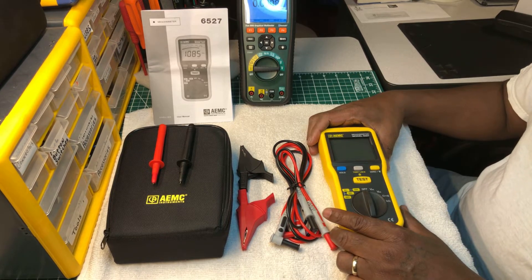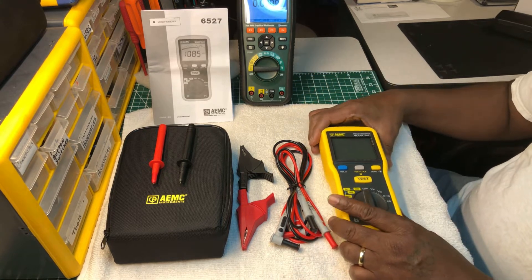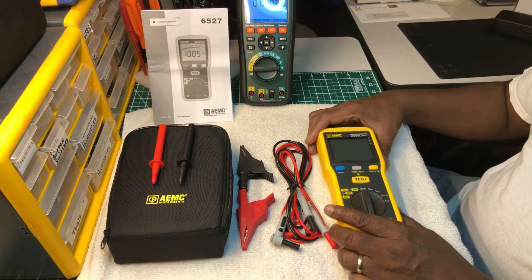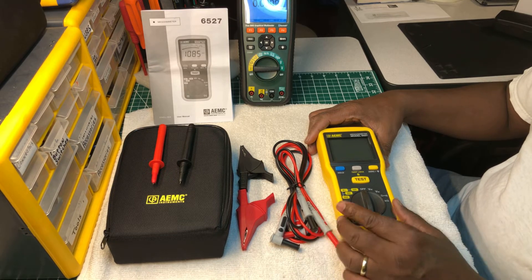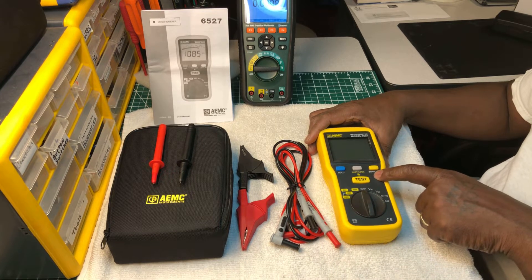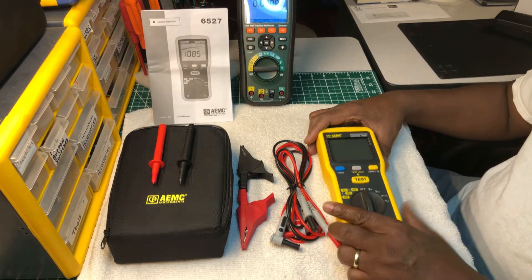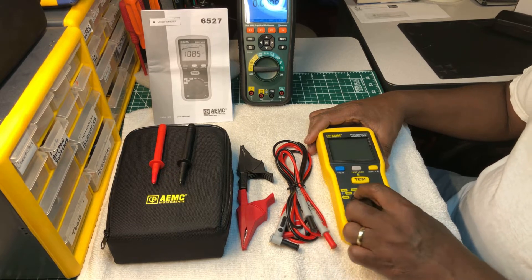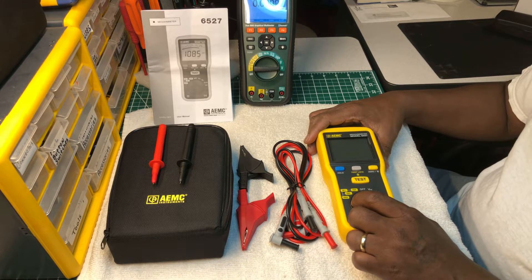This meter falls in the category of great and fantastic. This model doesn't have all the bells and whistles like PI — polarization index testing — or DAR testing, but you can still lock the test when you're taking a voltage during the insulation test. You can lock the voltage and count yourself to do the DAR testing or PI test manually.